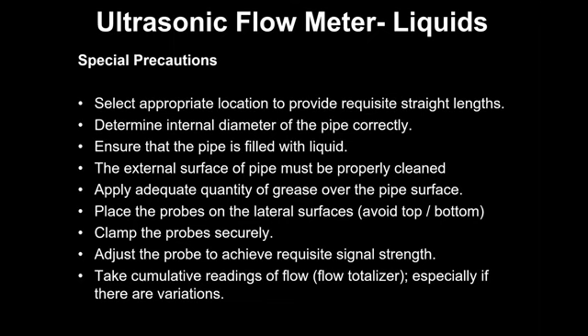So it has to be filled with liquid, otherwise the reading won't come. The pipe external surface should be clean. Grease should be applied properly so that there are no air gaps. The probe should not be placed on the top or bottom of the pipeline for obvious reasons. Normally the bottom is more corroded, and the top may have some issues. You should always go for a lateral surface. Clamp the probe securely.